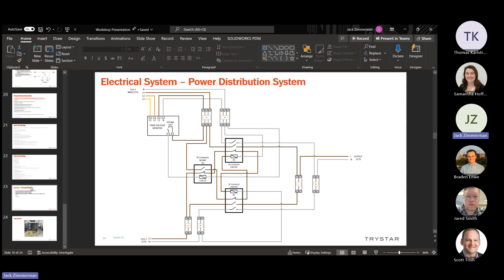Okay, now I get to show off this thing. I actually designed this with 4-pole in mind because I switch neutrals here. So we can do 4-pole, and I'm gonna help process that 4-pole quote—it should work because I'm not just taking the neutral from the common neutral, I'm taking it from both places and switching it through the contactors. So it's kind of set up for 4-pole already—it's just a matter of whether it will physically fit.